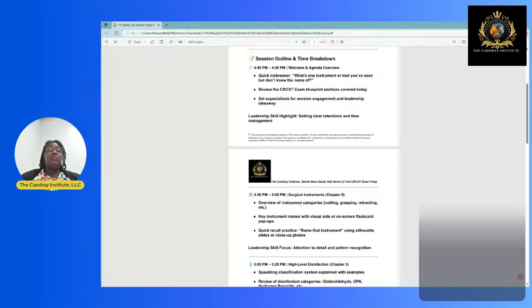Okay, we want to make sure that if there's any type of instrument tape on there that's color coded for identification, that it's in good condition. It's not dried out. It's not looking like it just went through a desert dust bowl. It isn't all crinkled up on the edges because it's lost every piece of moisture inside of it, okay? We want to make sure that the instrument is safe, because let's say we had that surgical instrument tape on our instrument during assembly. Now, we checked it for cleanliness. We checked it for workability, but we left that dried up, crinkly, old, dusty instrument tape on there.